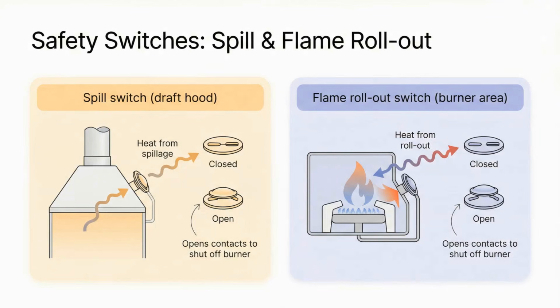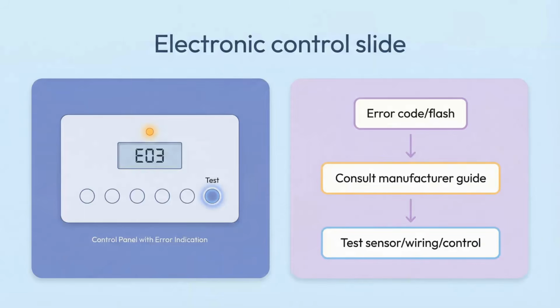Spill and rollout switches are thermal snap discs meant to shut the burner down during unsafe combustion conditions. A spill switch reacts to hot flue gases spilling from the draft hood relief opening. A rollout switch reacts to flame rolling out of the burner area. Both work by temperature rise opening contacts and interrupting the safety circuit. Electronic controls usually require very little routine service. Many have self-test functions, and when something goes wrong, they communicate through a flashing light or an error code. The correct approach is to use the manufacturer's troubleshooting guide to interpret the code, then test the indicated circuit, often a sensor, wiring, or the control itself.